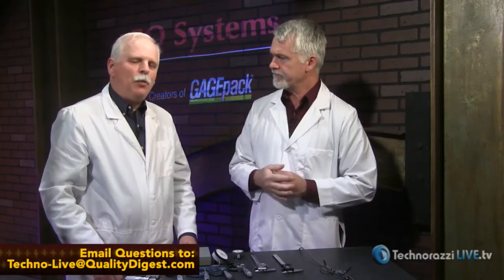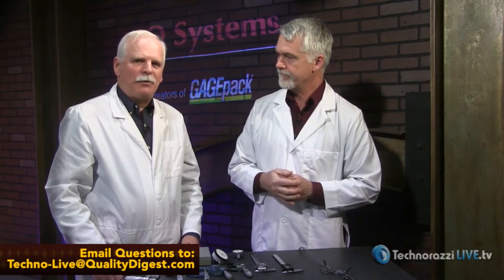Next up: what if you need to establish a calibration interval for a certain type of tool and the manufacturer doesn't specify one? Let's take a freezer or an oven as an example. If your quality program demands that everything you use to accept product, or certain key processes, be calibrated and in the system, you have to establish an interval. What's the right interval if the manufacturer doesn't have anything published in the owner's manual or that sort of thing? How do you go about doing that?